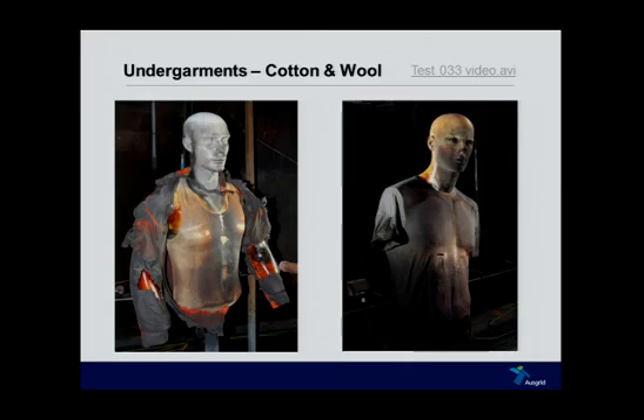Wool is excellent, wool is naturally flame retardant. You'll hear me use the two terms flame retardant and arc-rated. Flame retardant is tested for a flame, but it may not necessarily have been tested against an arc to get a calorie rating. So this woolen t-shirt hasn't been tested to get a calorie rating, so it's not arc-rated. So not all flame retardant fabrics are arc-rated, but all arc-rated fabrics are flame retardant. So wool is excellent, synthetics are out.